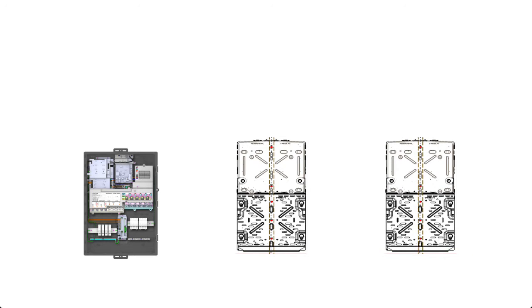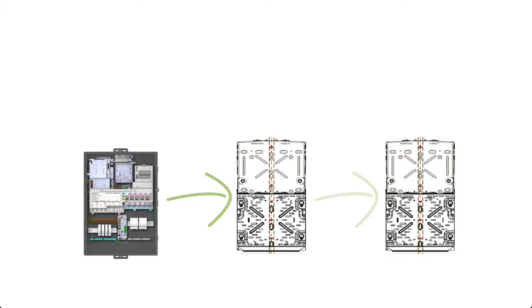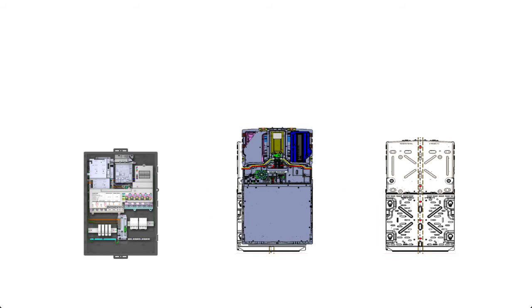Don't forget to allow for a minimum of 300mm clearance between each battery mounting bracket and also the system controller. Each battery can be safely fitted onto the battery bracket using the Enphase battery lifting handles.